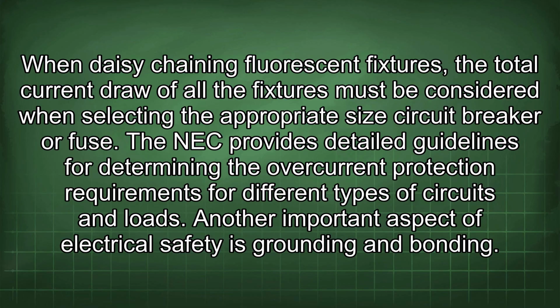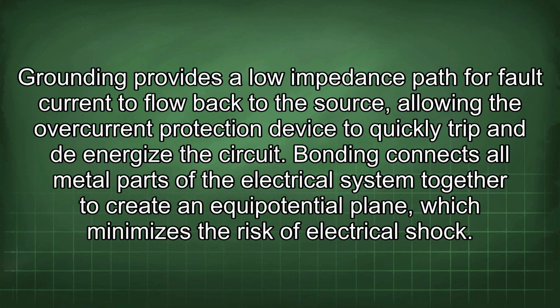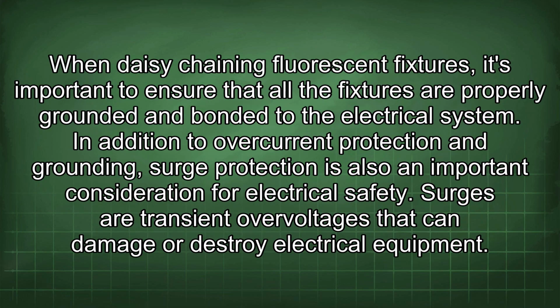The NEC provides detailed guidelines for determining the overcurrent protection requirements for different types of circuits and loads. Another important aspect of electrical safety is grounding and bonding. Grounding provides a low impedance path for fault current to flow back to the source, allowing the overcurrent protection device to quickly trip and de-energize the circuit. Bonding connects all metal parts of the electrical system together to create an equipotential plane, which minimizes the risk of electrical shock. When daisy chaining fluorescent fixtures, it's important to ensure that all the fixtures are properly grounded and bonded to the electrical system.